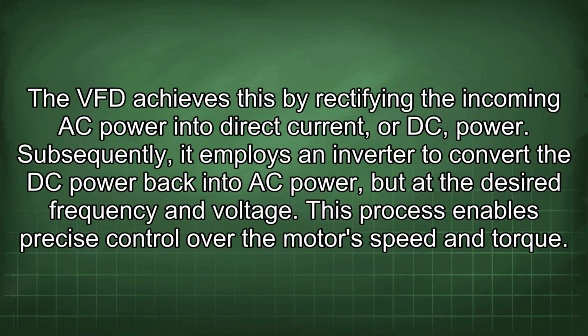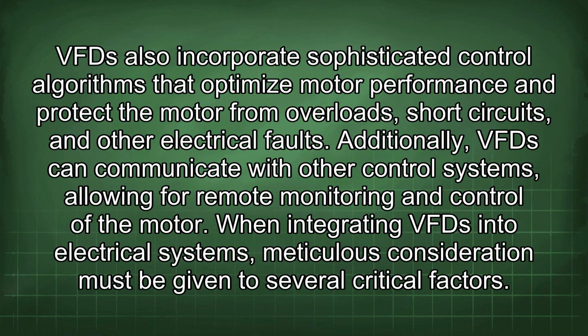The VFD achieves this by rectifying the incoming AC power into direct current, or DC power. Subsequently, it employs an inverter to convert the DC power back into AC power, but at the desired frequency and voltage. This process enables precise control over the motor's speed and torque. VFDs also incorporate sophisticated control algorithms that optimize motor performance and protect the motor from overloads, short circuits, and other electrical faults. Additionally, VFDs can communicate with other control systems, allowing for remote monitoring and control of the motor.